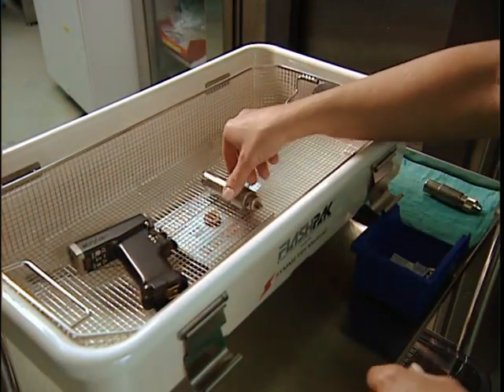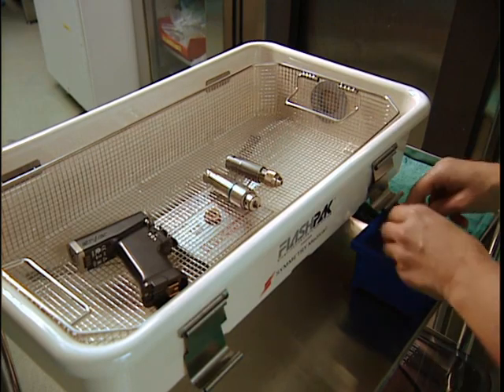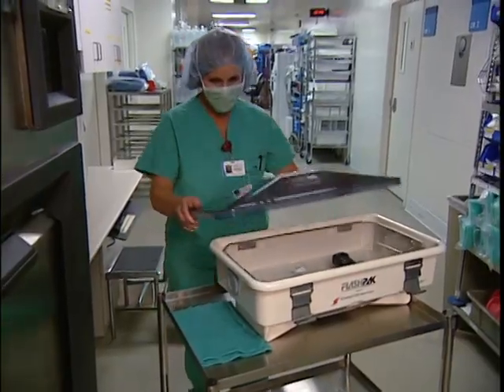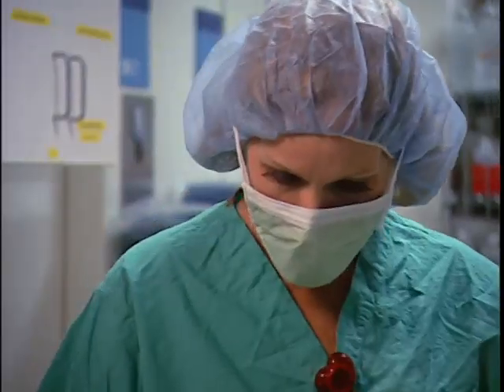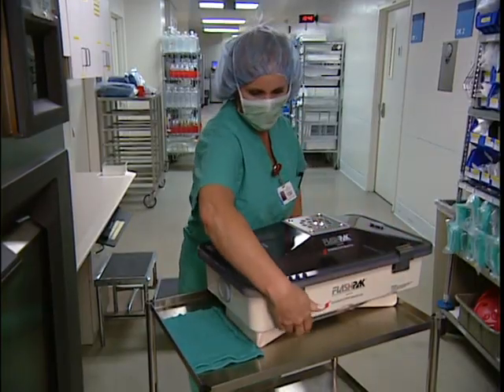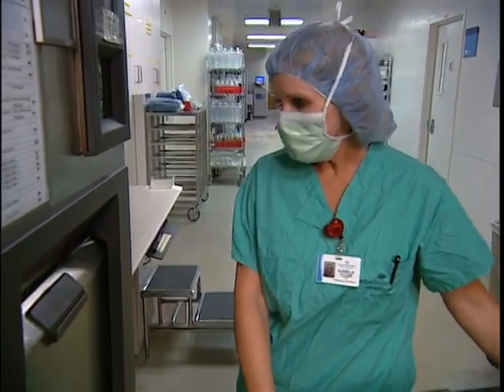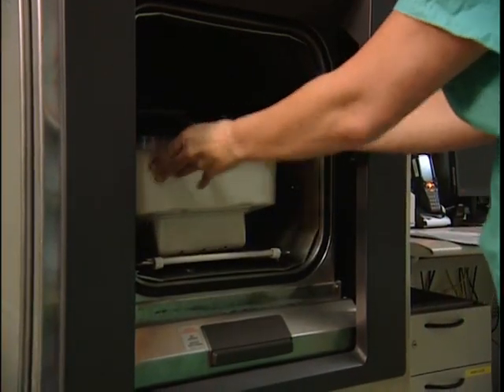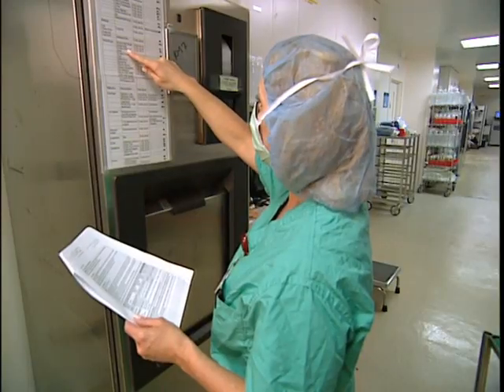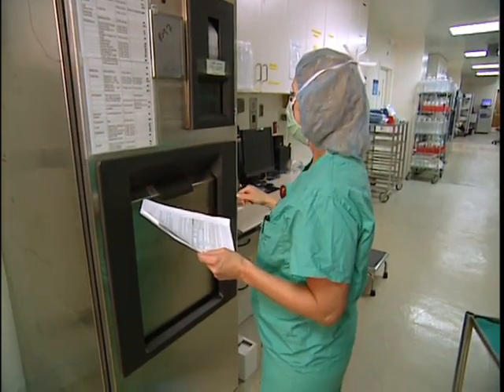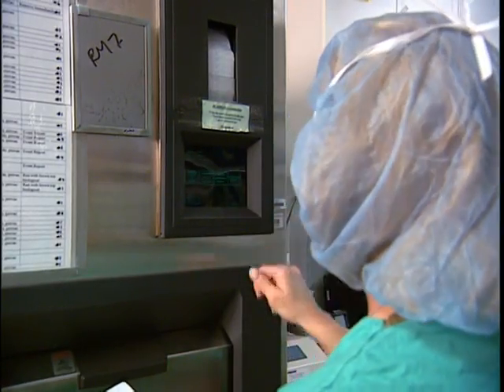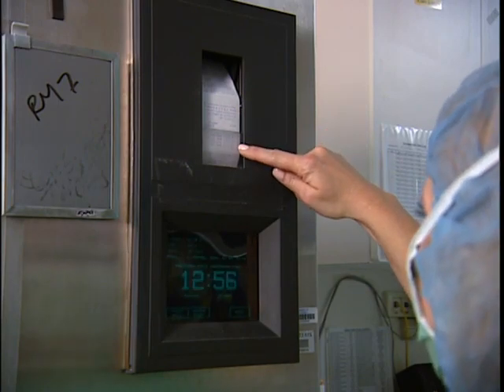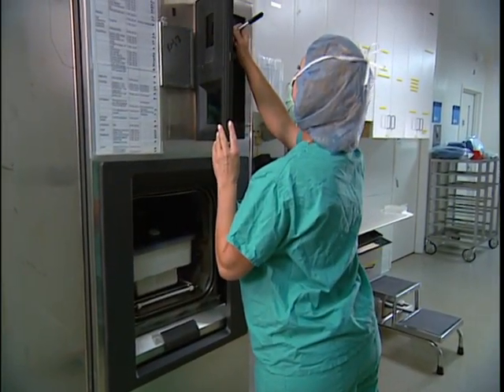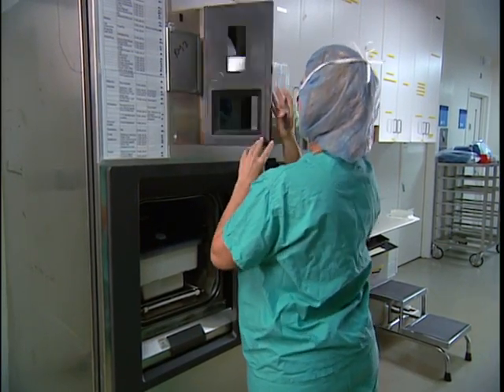In order to verify sterilization and ensure compliance with monitoring standards, be sure to use the correct process challenge devices, or PCDs. Use chemical and biological indicators as required. For example, a Class 5 CI should be used within each sterilizer container or tray for gravity displacement and dynamic air removal sterilizers. Follow the device manufacturer's written instructions on the specific method of sterilization, including cycle type, exposure times, temperature settings, and drying times, and periodically review the instructions for any updates. Remember that cycle parameters vary according to sterilizer type, and that monitoring of each sterilization cycle is essential. Indication of failure will require the device to be reprocessed and an investigation into the reason for the failure.